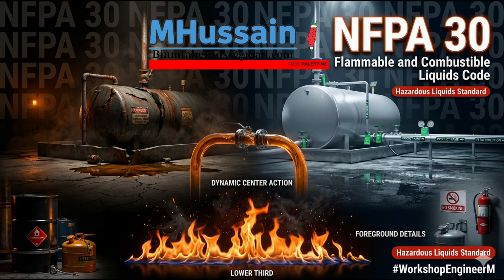So to eliminate that void space, engineers developed a floating roof tank. Instead of a static dome, the roof literally floats directly on the surface of the liquid hydrocarbon. It acts like a massive steel piston inside a cylinder. As pumps fill the tank, the liquid pushes the roof up. As it drains, the roof rides the liquid all the way down. It is a phenomenally elegant solution to a massive thermodynamic problem. Because the steel roof is resting directly on the liquid, there's virtually zero void space. No trapped air, so no oxygen available to mix with the vapors. By taking atmospheric oxygen out of the equation, you completely neutralize the explosive potential inside the tank. And because the internal risk is so much lower, NFPA 30 lets you space floating roof tanks slightly closer together.